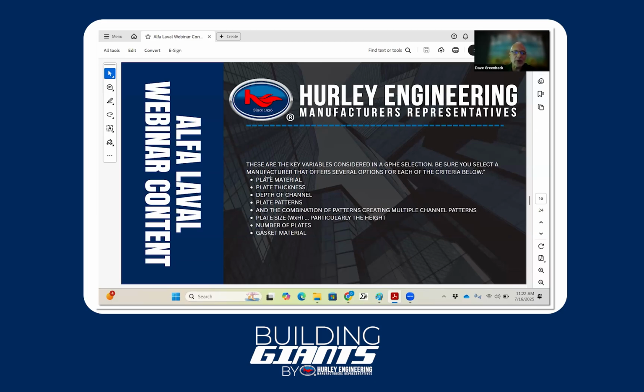The plate material and plate thickness are driven by the application, same with the gaskets. But depth of channel and the plate pattern, and whether you have a combination of plate patterns, is really important to ensure even flow, even distribution, and turbulence in all your operating conditions. So you want a manufacturer where you can select your plates, but then run it at different conditions to make sure you're covered for those lesser flows.